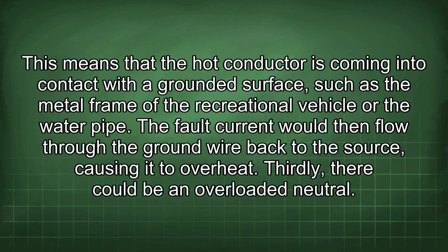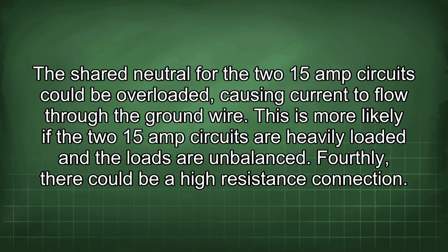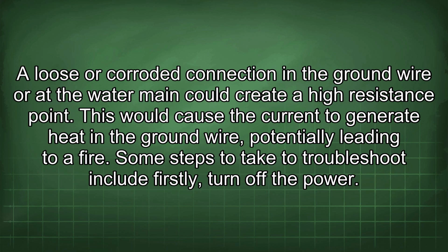The fault current would then flow through the ground wire back to the source, causing it to overheat. Thirdly, there could be an overloaded neutral. The shared neutral for the two 15 amp circuits could be overloaded, causing current to flow through the ground wire. This is more likely if the two 15 amp circuits are heavily loaded and the loads are unbalanced. Fourthly, there could be a high resistance connection. A loose or corroded connection in the ground wire or at the water main could create a high resistance point. This would cause the current to generate heat in the ground wire, potentially leading to a fire.